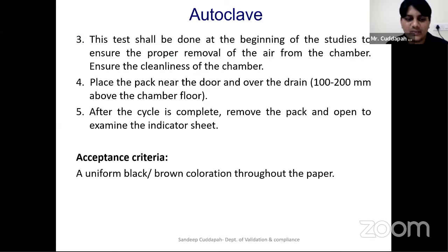As I told you, for the Bowie-Dick test, the acceptance criterion is that it will uniformly change the color of the indicator. For each test, you have to define the procedure and the acceptance criteria, and you will verify whether you achieved that criteria during performance qualification. The same thing you will do in requalification also. But the difference between performance qualification and requalification is that you will do the same test during requalification, but in performance qualification you will do it 3 times to make sure the equipment is giving consistent results.